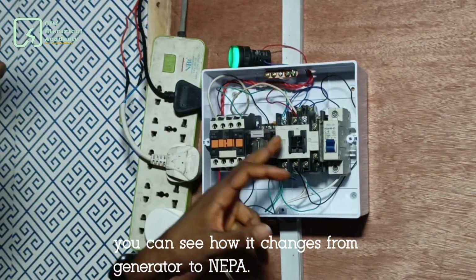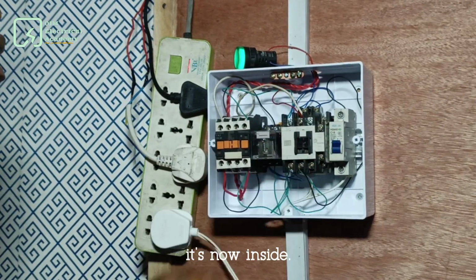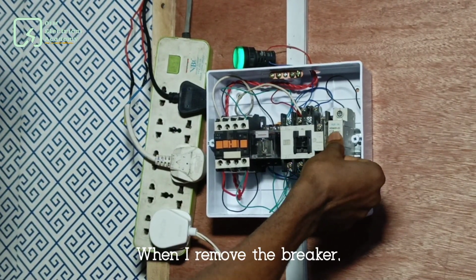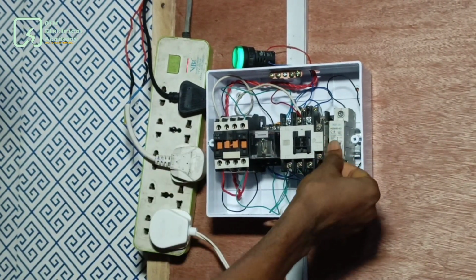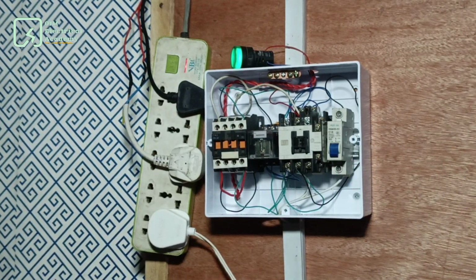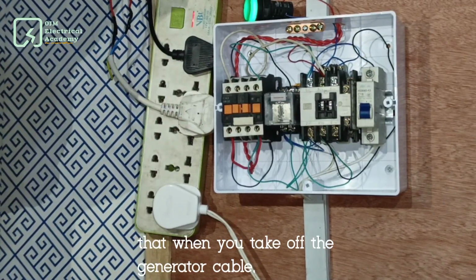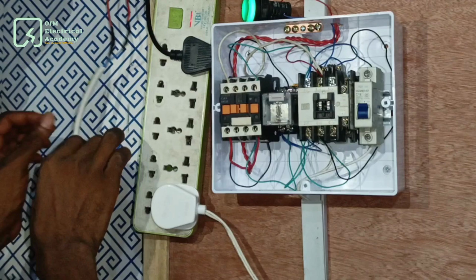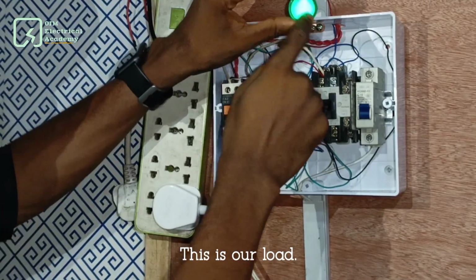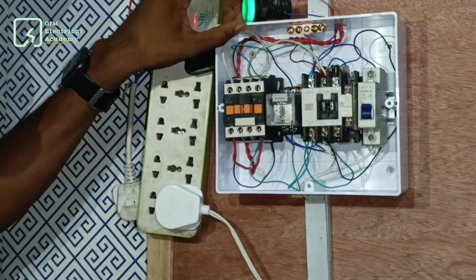So when I turn it on, you can see how it changes from generator to NEPA. NEPA is now on, it's now inside. When I remove the breaker, this guy goes in. You can see how it goes in. So you will notice that when you take off the generator cable, the power is still on. This is our load. Power is still on.